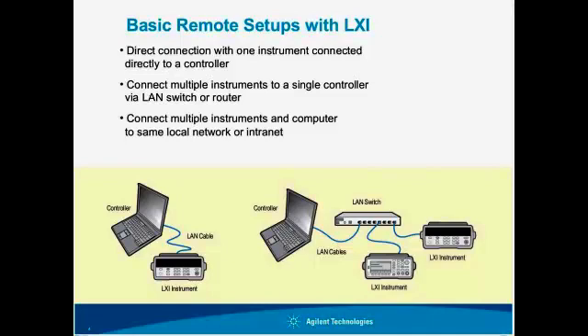What if I want to set up a test system to control multiple instruments? I add in either a router or a LAN switch. A LAN switch is the easiest way — it's a relatively simple network device that routes packets where they need to go. It allows me to connect my computer and multiple instruments, and now I have my LXI test system.